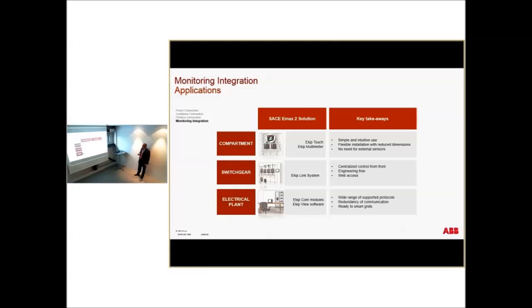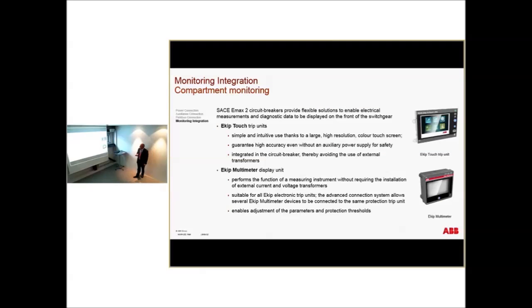Ekip Link, I'll show you later on how it works. And then you have a standard communication, which you are familiar with. The compartment monitoring basically is a simple, intuitive, high-resolution color touchscreen we described before. It is very accurate, and is integrated in the circuit breakers to avoid the use of external transformers. The multimeter display is 95 by 95, and it can replicate exactly what is done by this one. The important point is that you need just one cabling, one power supply, and then from that it goes inside the breaker.